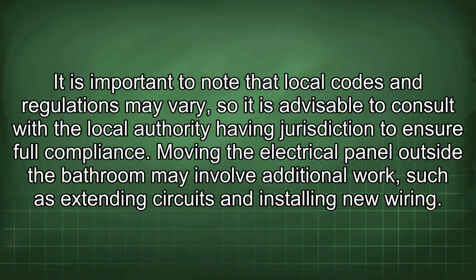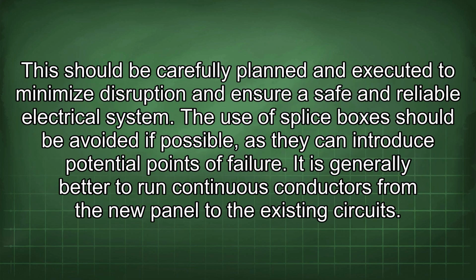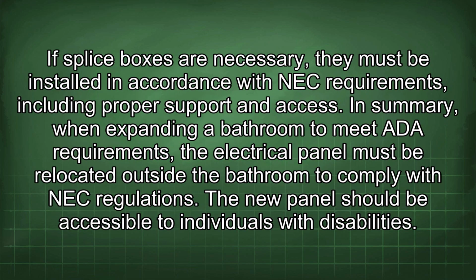Moving the electrical panel outside the bathroom may involve additional work, such as extending circuits and installing new wiring. This should be carefully planned and executed to minimize disruption and ensure a safe and reliable electrical system. The use of splice boxes should be avoided if possible, as they can introduce potential points of failure. It is generally better to run continuous conductors from the new panel to the existing circuits. If splice boxes are necessary, they must be installed in accordance with NEC requirements, including proper support and access.